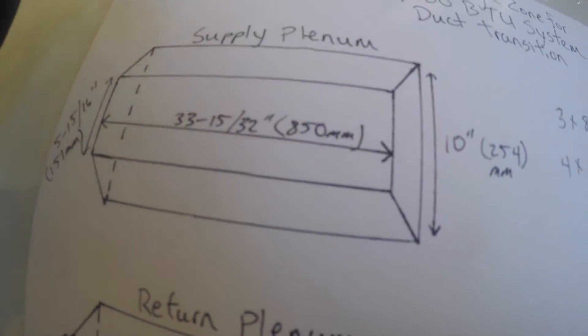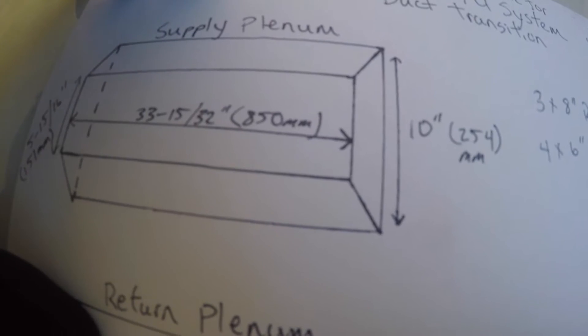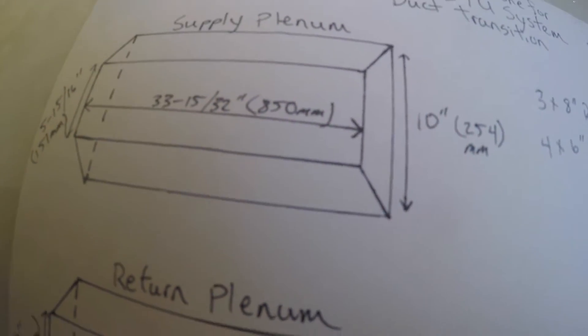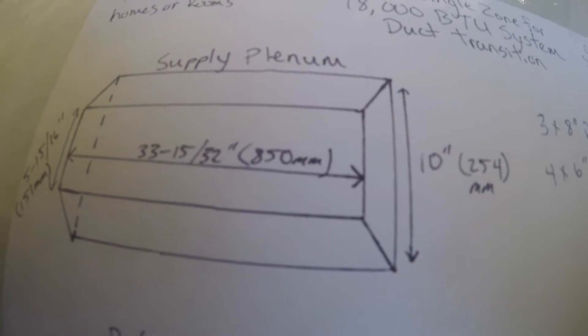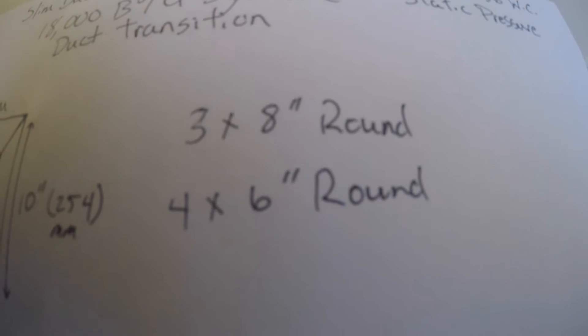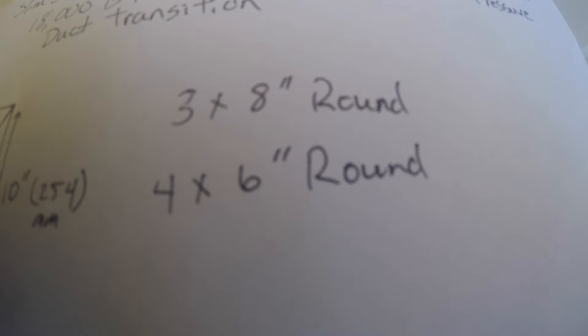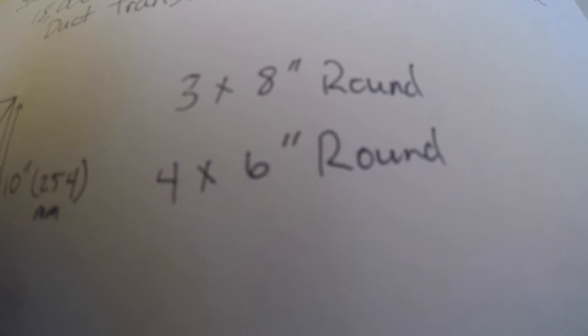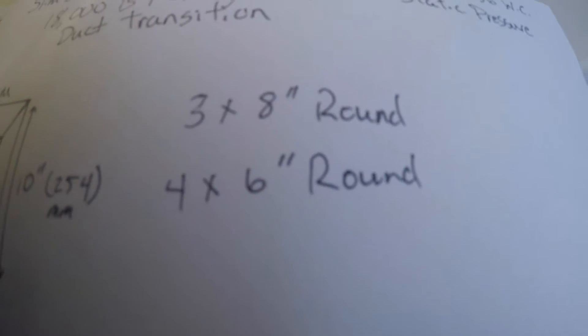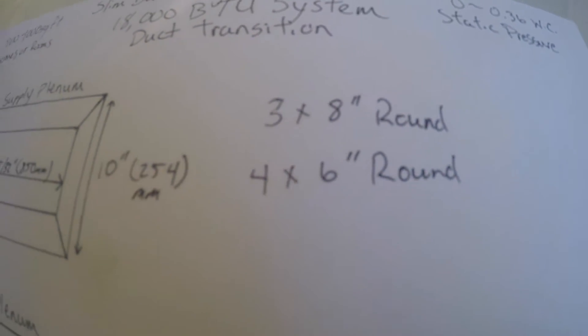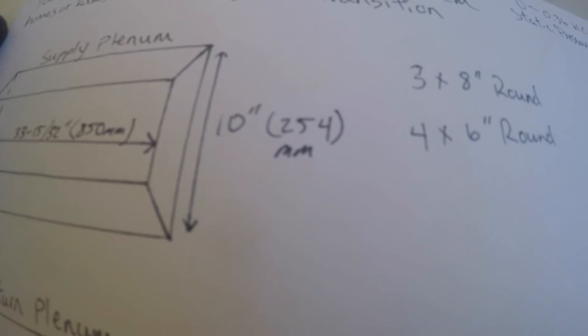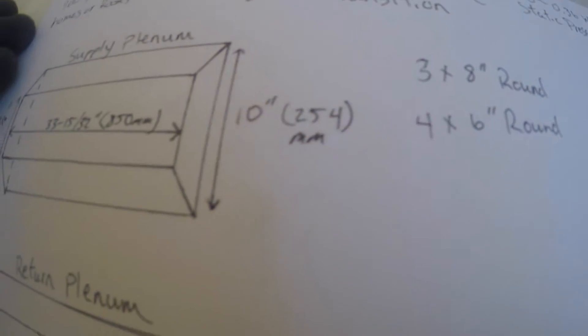so that we could basically cut a round duct on that 10-inch circular surface area. Ducts that would work in this type, based on the static, would be either three 8-inch rounds or four 6-inch rounds. Of course, we want to keep our distance on our ducting less than 15 feet per run, and that would keep our static pressure fine.